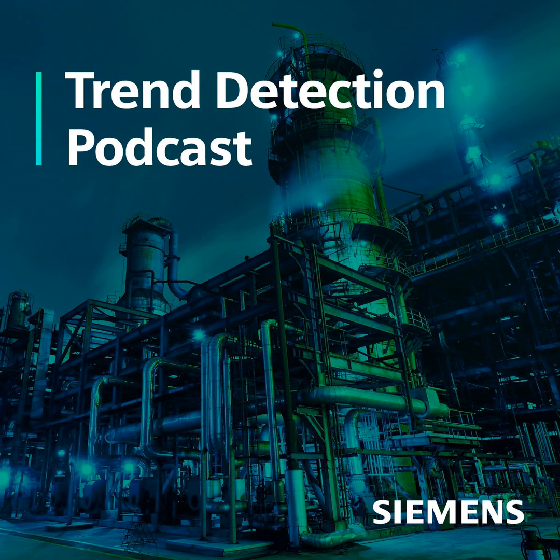Senseye, in my assessment so far, is the first tool to be able to go through the gates of normal condition monitoring and catch anomalies within those barriers. And so I usually talk about the three gates of control. The first gate of control is you buy a motor, and that motor would be a 22 kilowatt motor, has got defined variables. It can only go up to 45 amps. It can only do a certain speed.